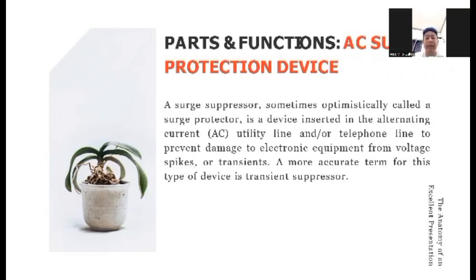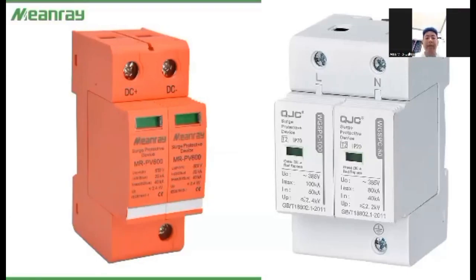AC surge protection device. A surge suppressor, sometimes mistakenly called a surge protector, is a device inserted in the alternating current utility line and or telephone line to prevent damage to electronic equipment from voltage spikes, or we can call them transients. A more accurate term for this type of device is a transient suppressor. So, this is the surge protection device. It is a device inserted in the alternating current utility line, for the telephone too, to prevent damage to our electronic equipment from voltage spikes. Next. So, this is what it looks like. On the left side, the orange one is a DC surge protection device, and the white one is an AC surge protection device. There. Next.